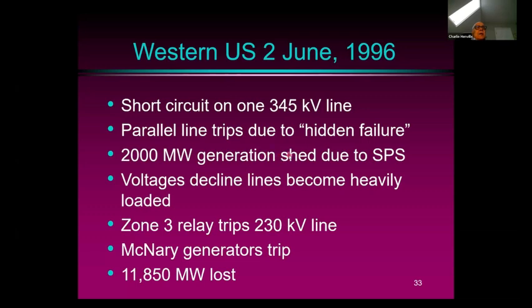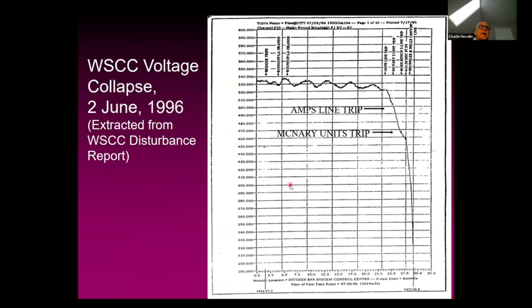So the generation being tripped offline was intentional, but the voltages started to decline very quickly as the lines became heavily loaded. As is often the case, a protective relay operated unexpectedly when the power system was under stress. This zone 3 is a transmission line protective relay, which tripped a 230 kV line. And then some generators at McNary Generating Station also tripped offline. So in that case, nearly 12,000 megawatts of generation was lost. That was a very severe event. And here we see the voltage at a certain point in the system where the voltage was being monitored. And this here is 525 kV.